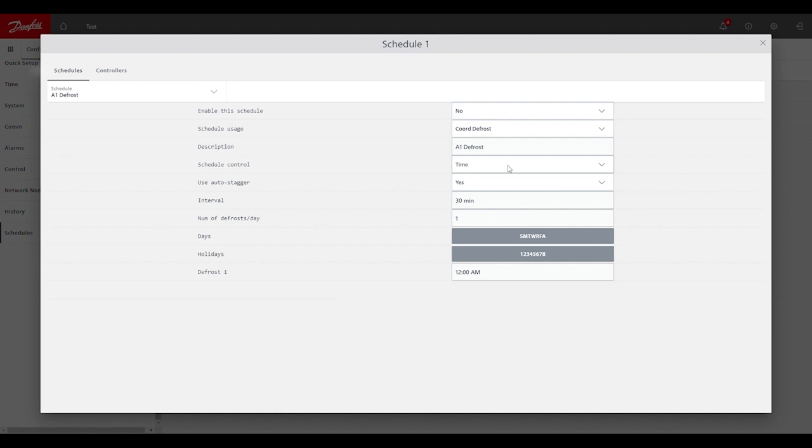Schedule control, we could defrost off a digital input if we wanted to, but time is most common. Staggering would allow us to stagger defrosts across multiple schedules or multiple case controllers. So if we have 20 cases in a store, this would help to make sure they're not all defrosting at the same time. And interval would be that spacing between one defrost grouping to the next.